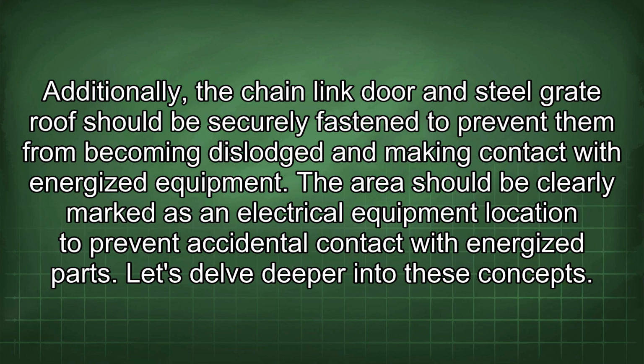Additionally, the chain-link door and steel grate roof should be securely fastened to prevent them from becoming dislodged and making contact with energized equipment. The area should be clearly marked as an electrical equipment location to prevent accidental contact with energized parts. Let's delve deeper into these concepts.